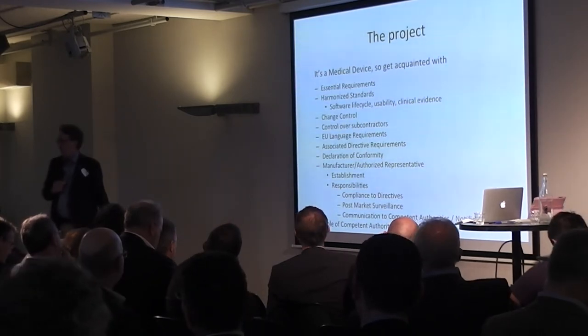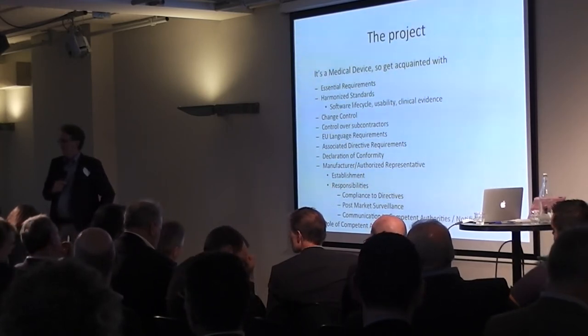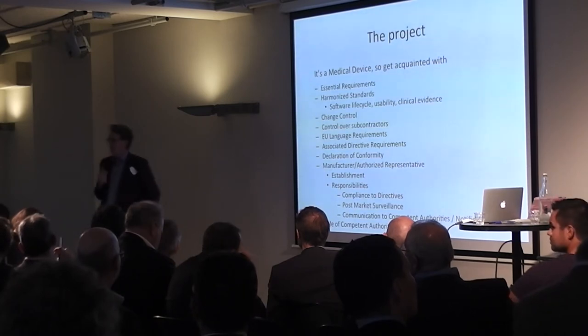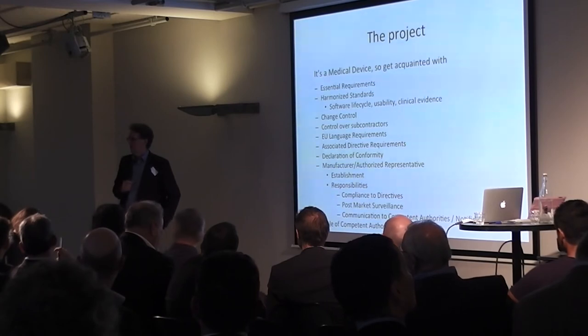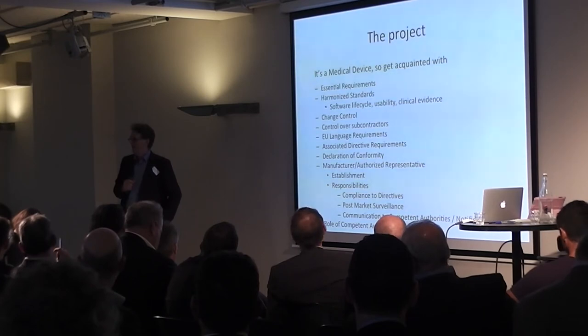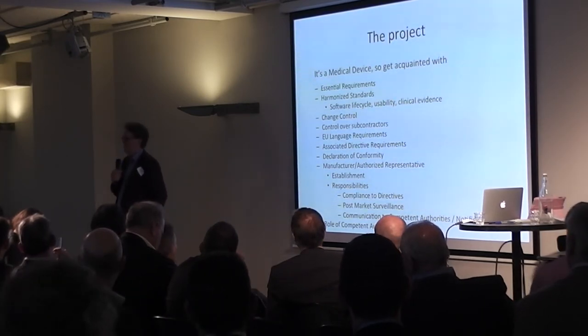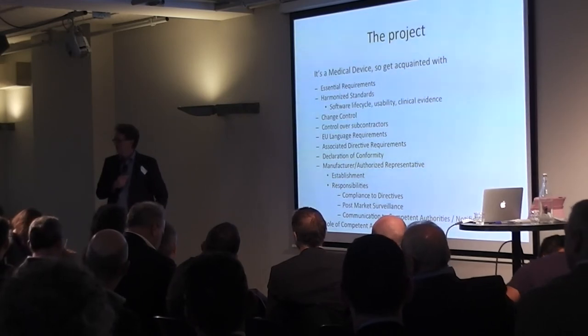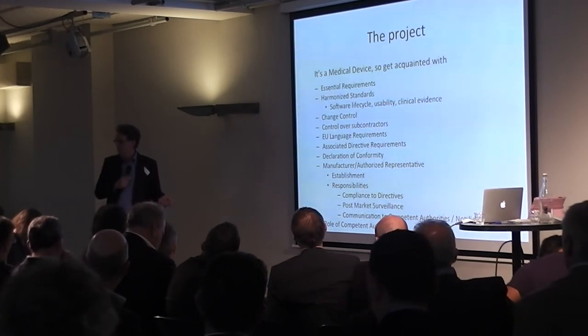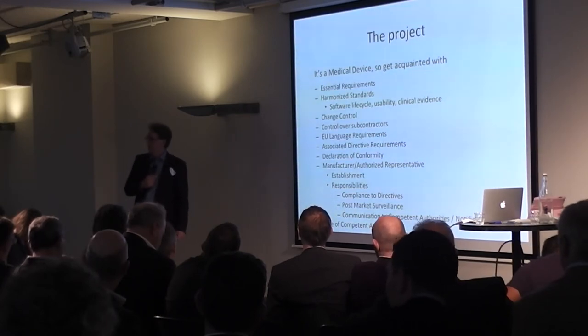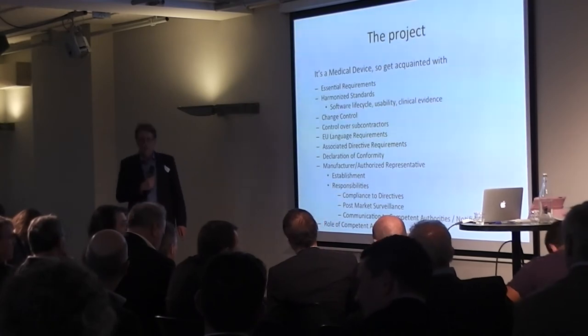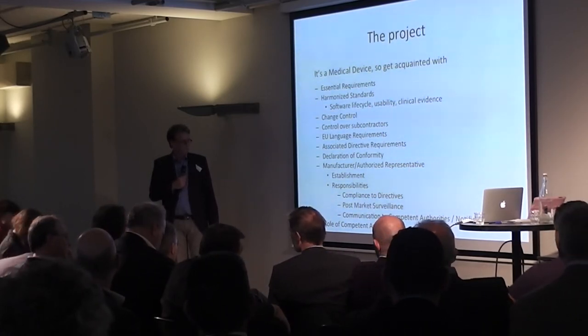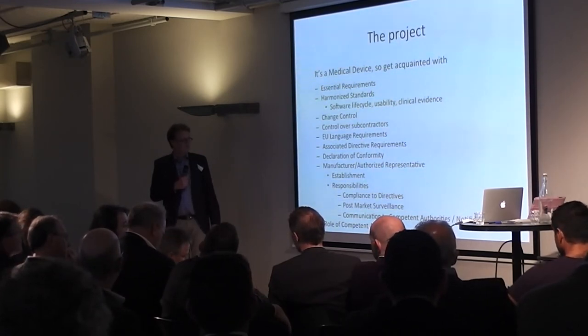Question about the language requirement: very often with software, you notice that the English version is much better than the Dutch translation. Does this rule say something about the quality of translation, or just that it needs to be translated? It's important that you provide the product in the local language. You can always build in a language switch option for the user to go to English if more convenient. But a translator is a subcontractor that you need to control — if you have a bad translator producing bad translations, something is not going right in your quality system.